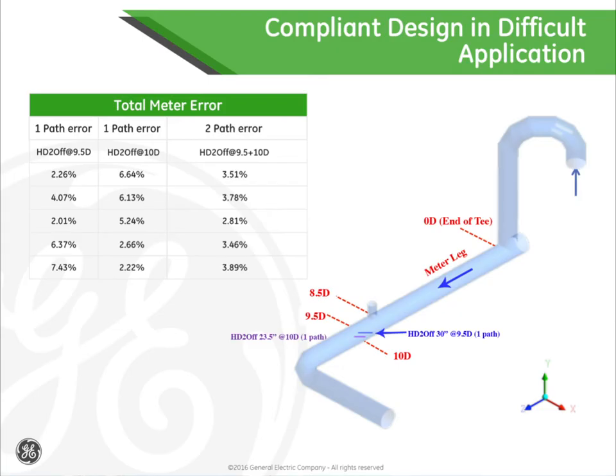As Randy just spoke about, there are many challenges to overcome when making a flare measurement. One such application I would like to reference is the designing of a flare meter in a refinery in California in a 42-inch header for compliance to local and federal regulatory requirements. Not only is this an application where the meter is being installed with less than ideal straight run, only 12 total diameters available, the process ranges from a molecular weight of 4 to 65 grams per mole.